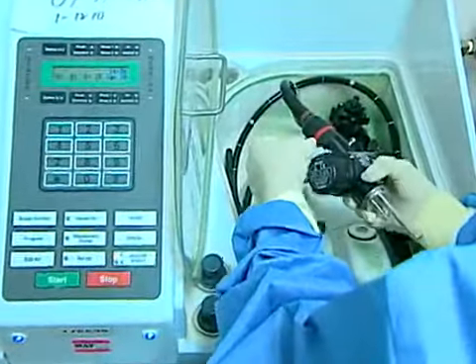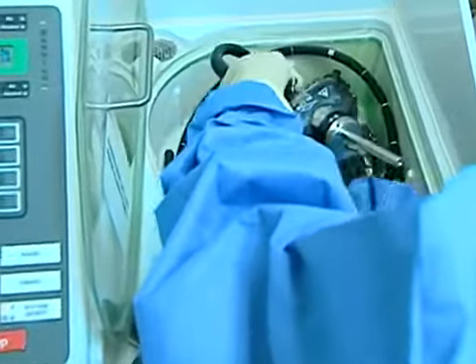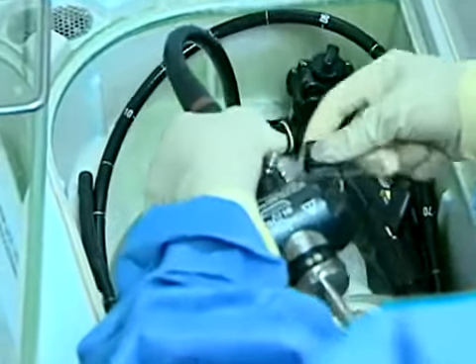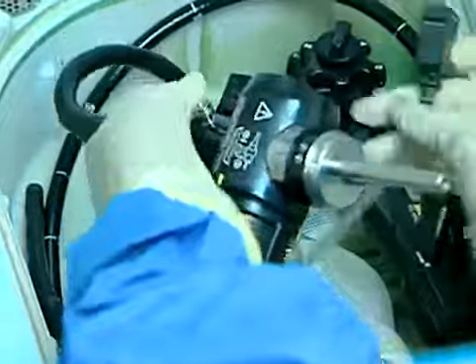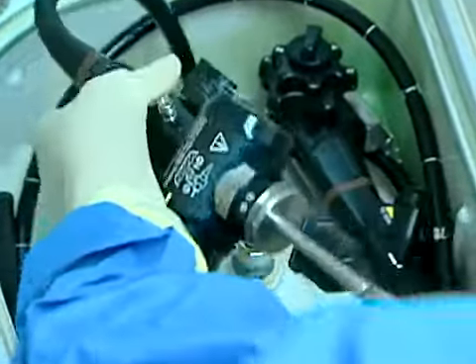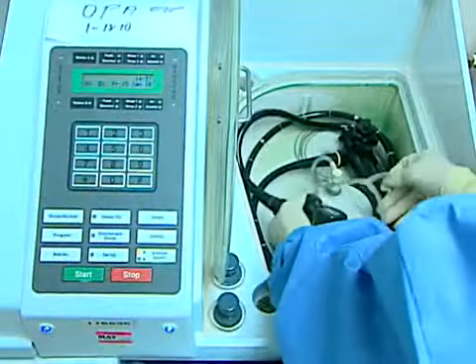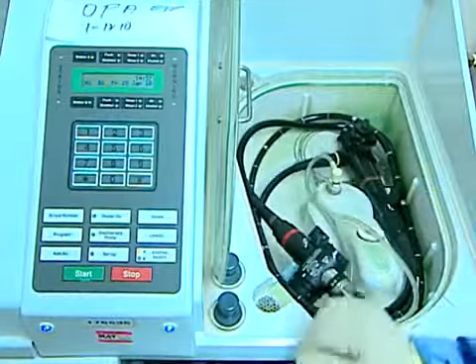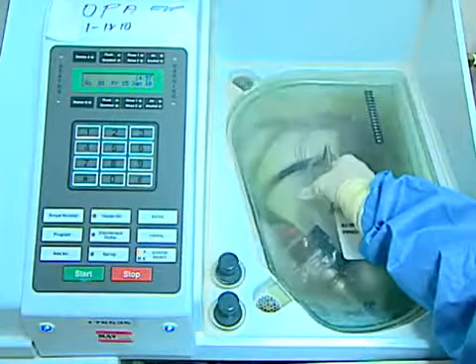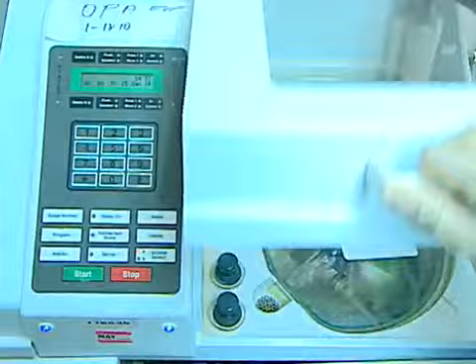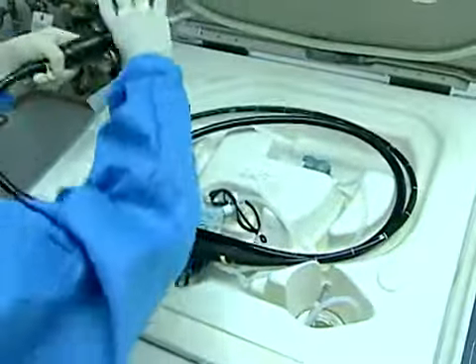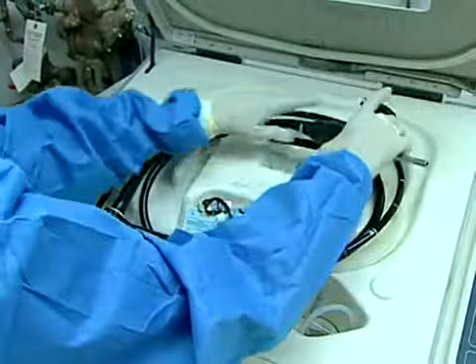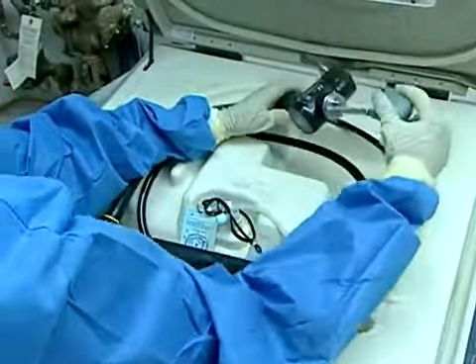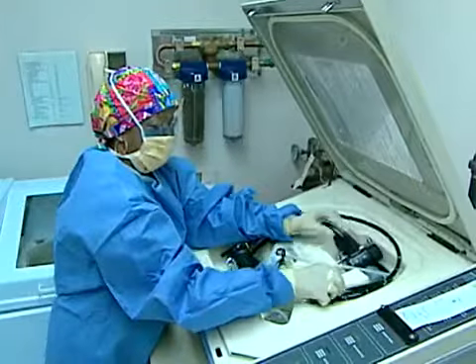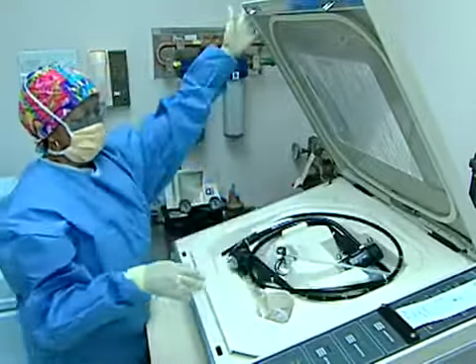Be sure your automatic endoscope reprocessor or sterilizer is compatible with the endoscope and that the connecting parts of these devices fit properly. Finally, be sure that endoscopes or accessories that will come in contact with sterile tissue are sterilized before each use, and that endoscopes that are going to come in contact with intact mucous membranes in the respiratory and GI tracts, for example, undergo at least high-level disinfection before each use.